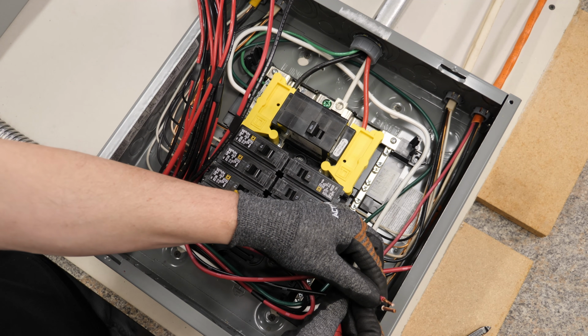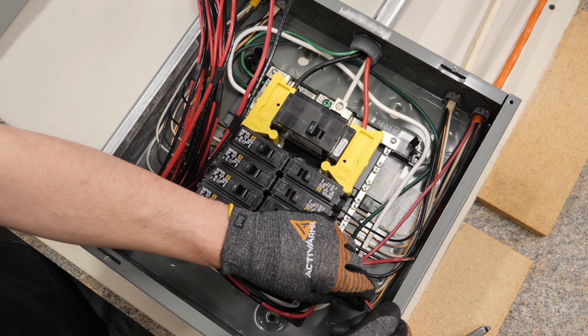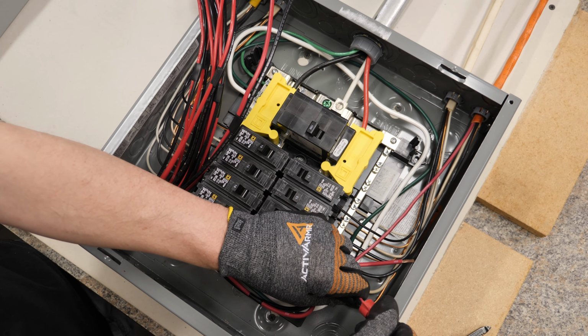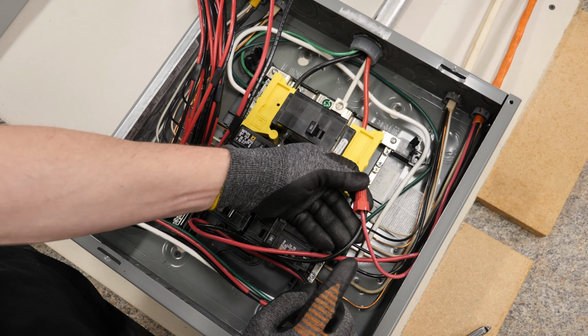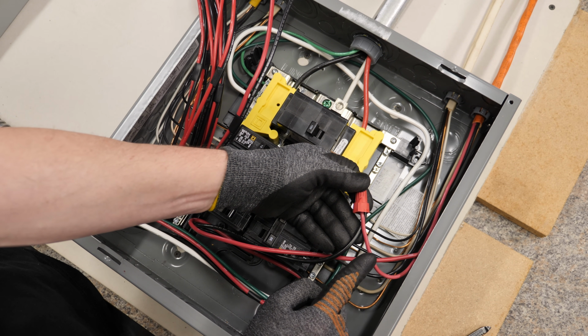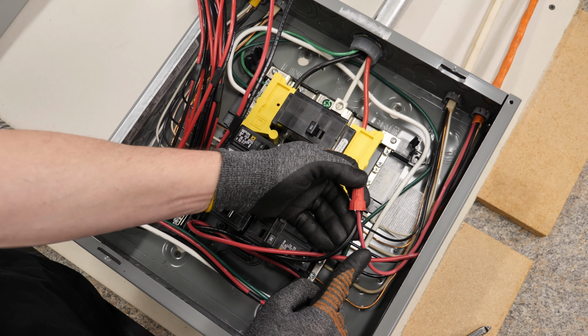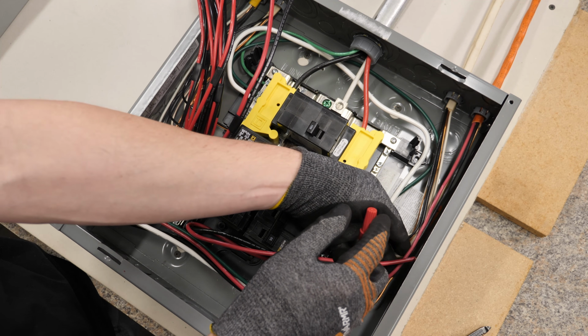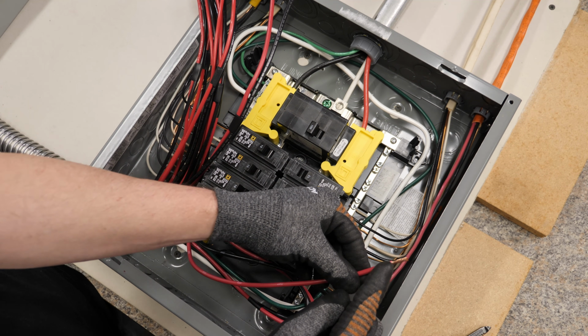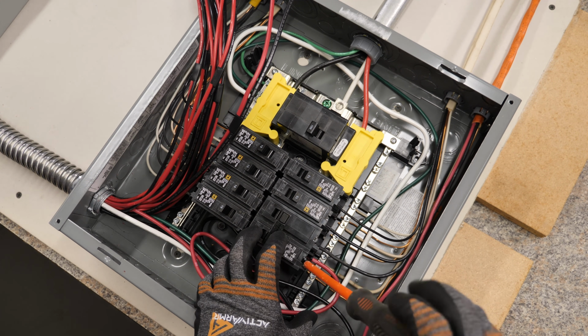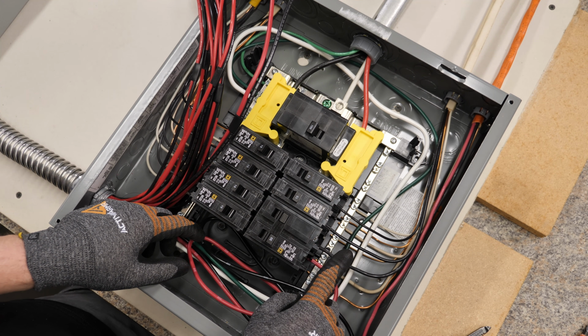All we need to do is put a wire nut on these two right here. There we go - our black wire is connected to our load, which is the 240 volt well pump. We'll push that out of the way, and the red wire goes up to the circuit breaker. Next one is L1.